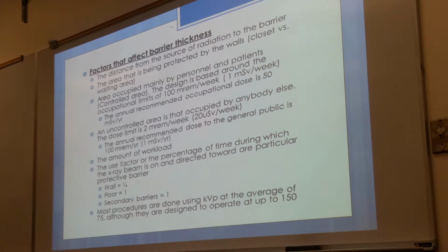The area occupied mainly by personnel and patients, this is the controlled area. The design is based around the occupational limits of 100 millirems per week. As a side note, the annual recommended occupational dose is 50 millisieverts per year.